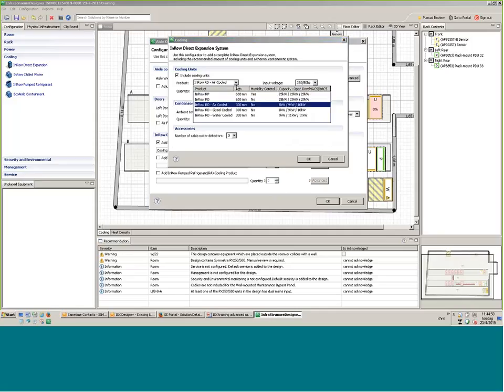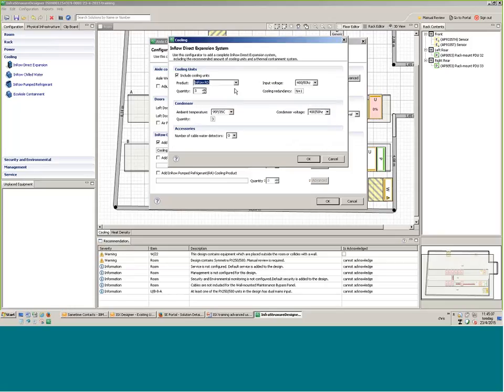For each RD, when you select it, be aware that you also have a minimum load. So like the RD 600, the big one, has a minimum load of 10 kilowatt. Otherwise, the compressor would start and stop all the time, and this would give you a problem. Since last year, we have a firmware that lets them be in hot standby. So they can actually, in communication, say, here, we know we don't have enough load, let's have 1 or 2 run, and then the other is waiting until the load is getting there and jumps in. So this is, of course, possible.